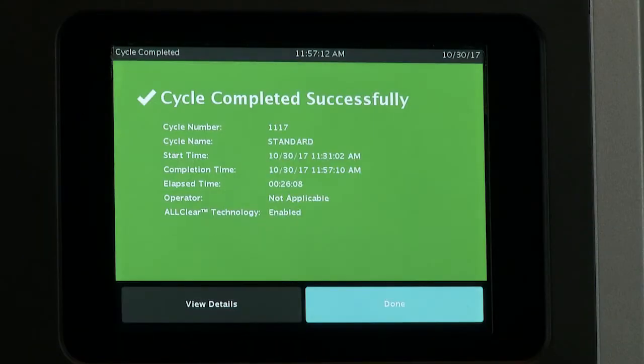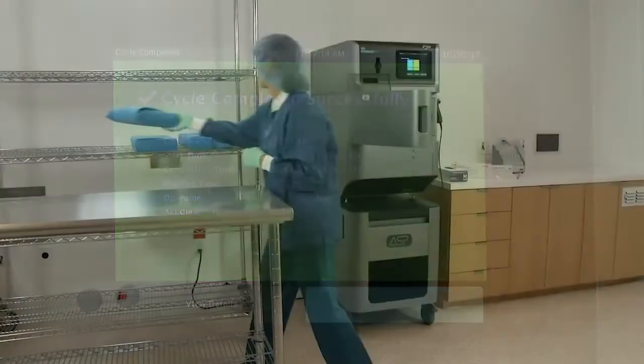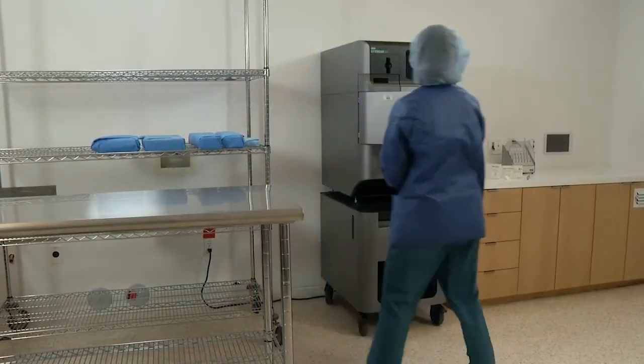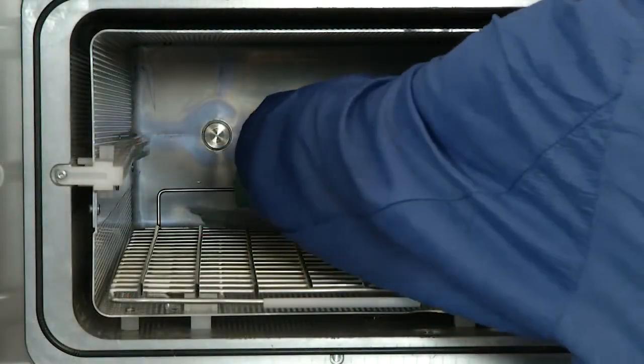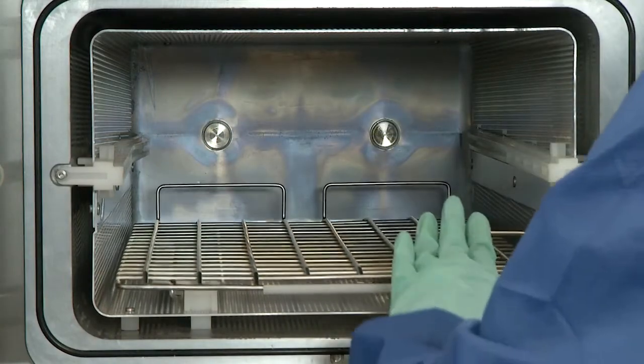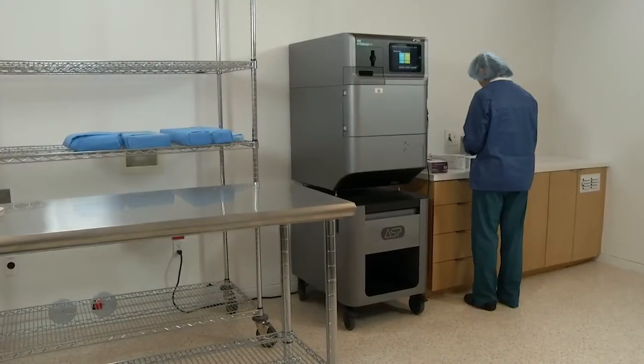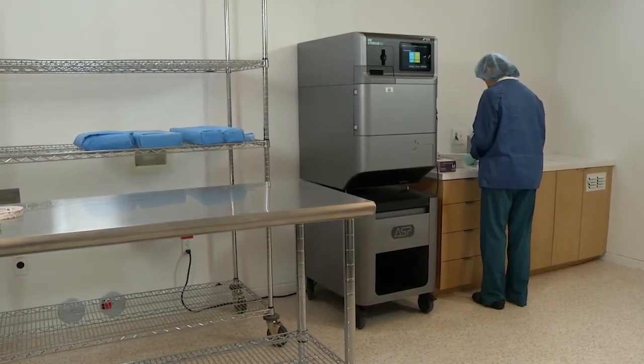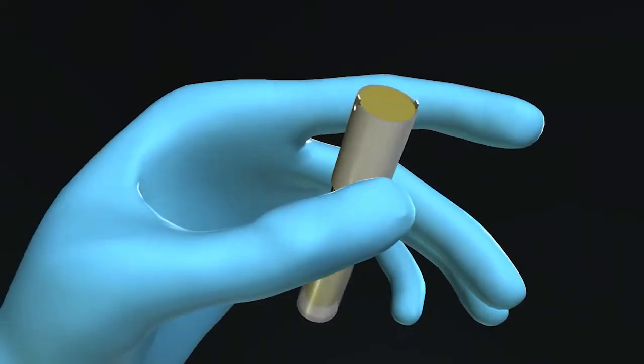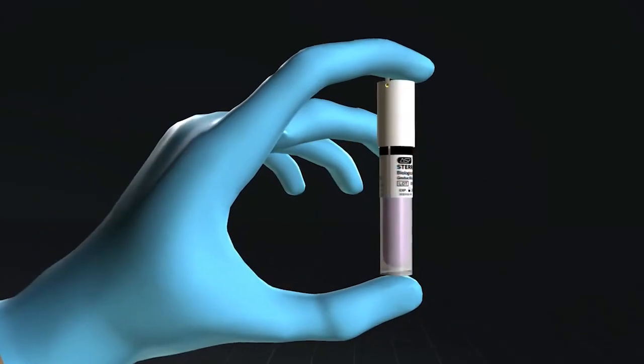Step 5. Once the cycle is complete, put on protective gloves and remove the Tyvek pouch from the sterilizer. Remove the STERRAD CycleSure 24 biological indicator from the pouch. Review the instructions for use to ensure its proper use.